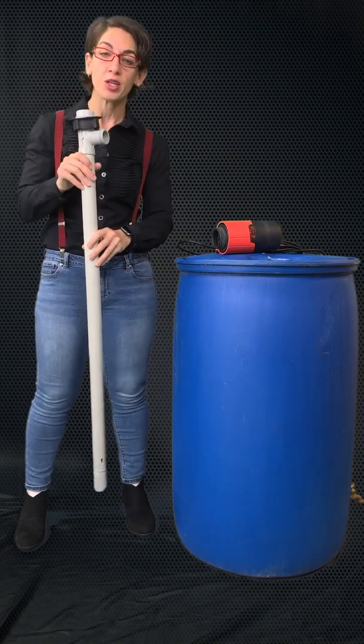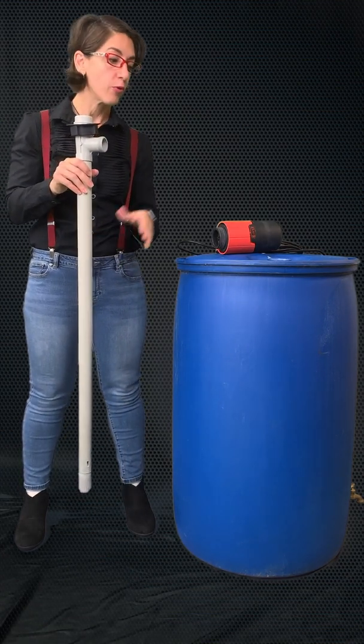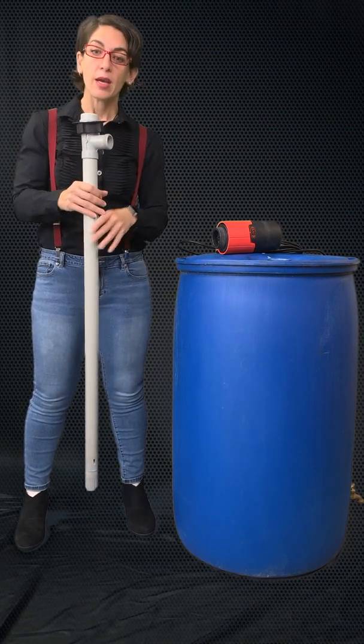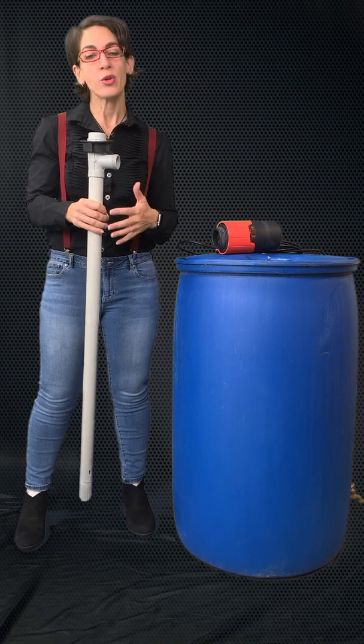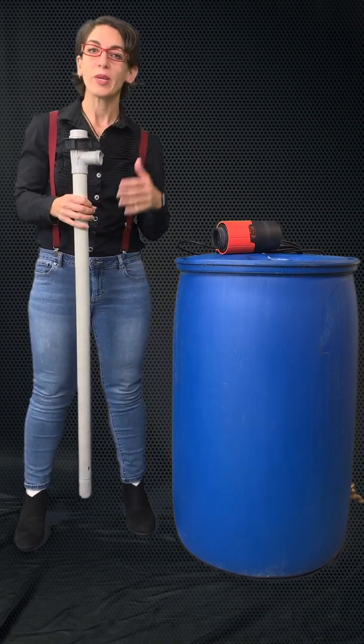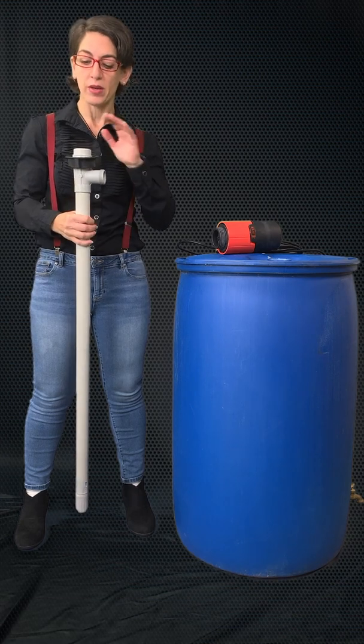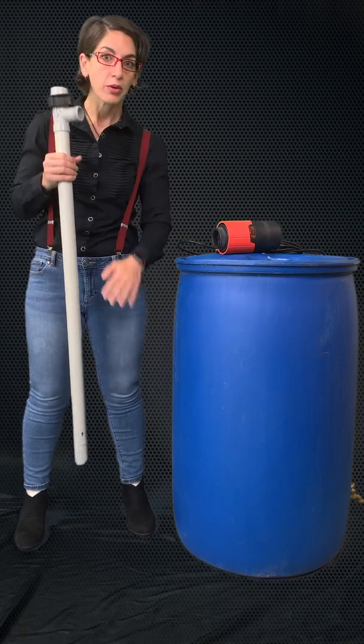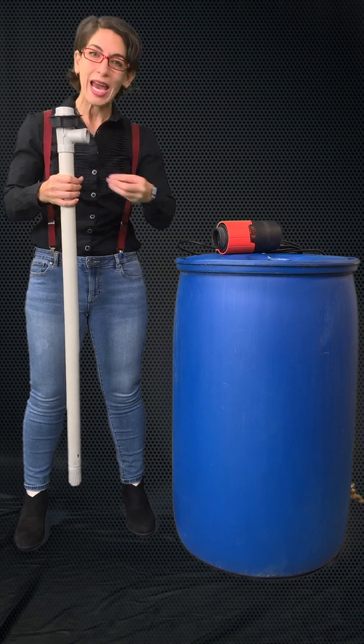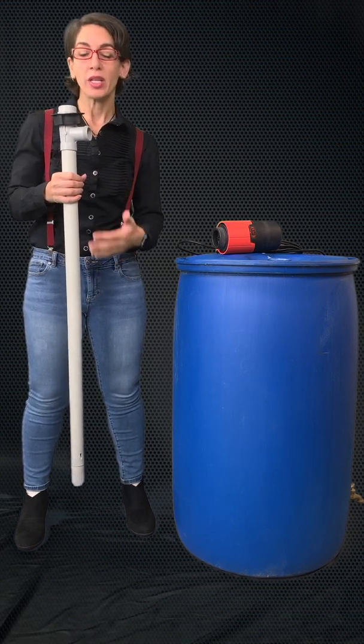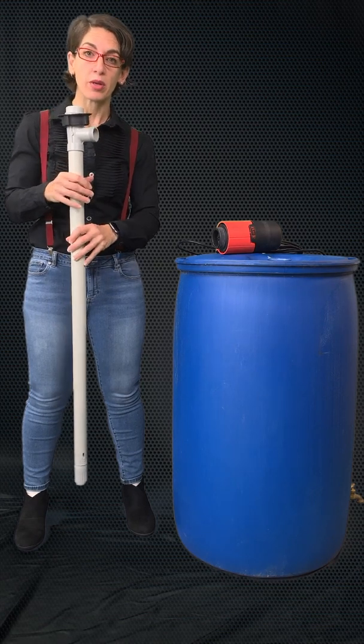So again, this is the 39-inch polypropylene length pump for a 55-gallon standard drum pump. Another difference: Flux designs their drum pumps to be repairable. If you've ever experienced another brand out there, a lot of times if the coupling or the impeller isn't the issue, you can't really repair it anymore. You can't really access the inside of the drum pump if the shaft failed or any of the sleeves inside or the bearings fail.